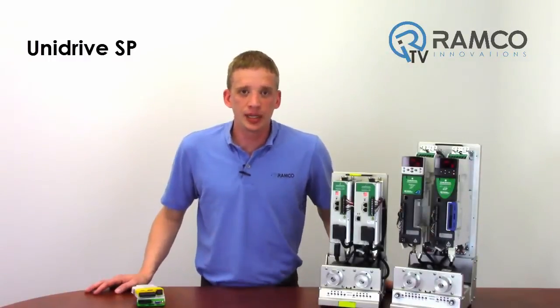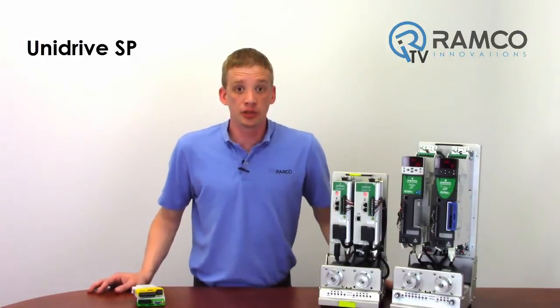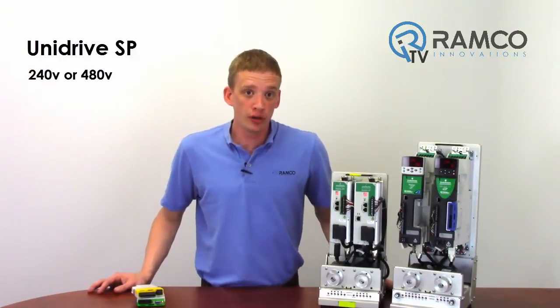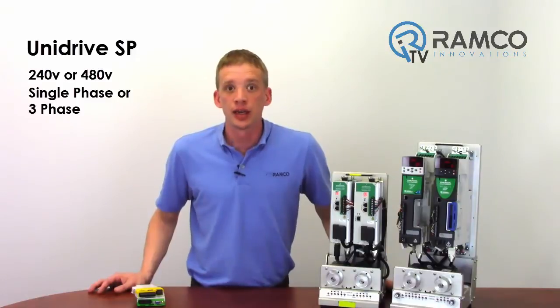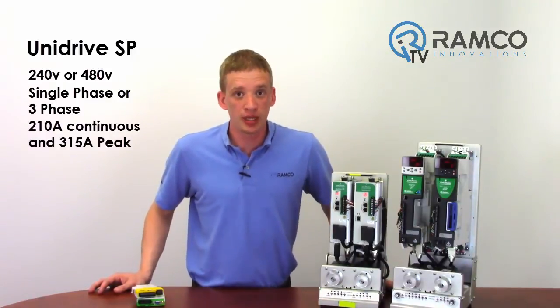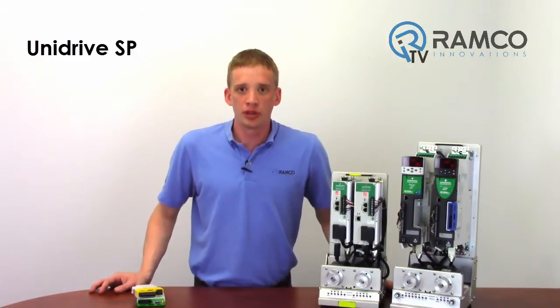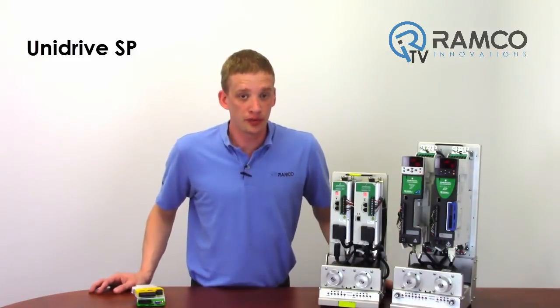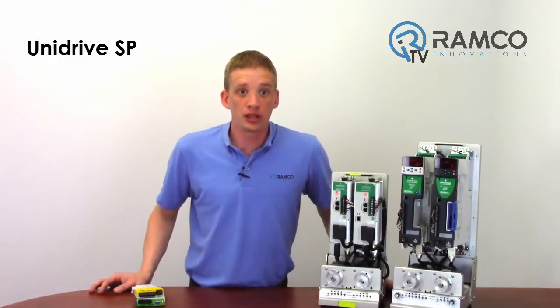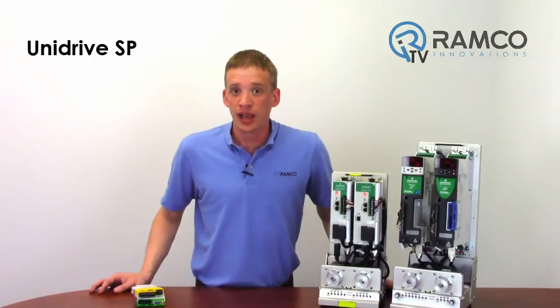The Unidrive SP is inherently a VFD, but with the addition of a solution module it becomes a servo drive. These drives are rated 240V or 480V AC, single phase or three phase, and go all the way up to 210A continuous and 315A peak. I typically use these drives for larger applications when the servo exceeds the current requirements of the Digitax. The Unidrive SP offers a lot of the same features the Digitax does, including safe torque off and solution modules.